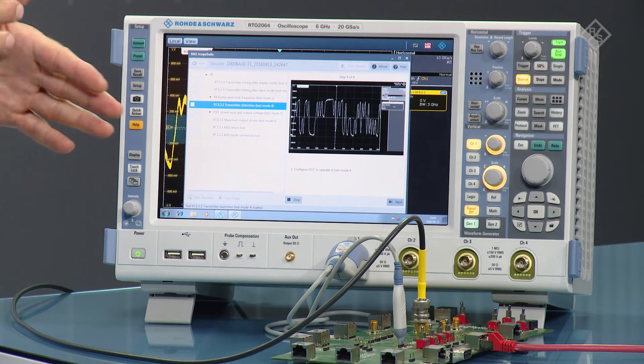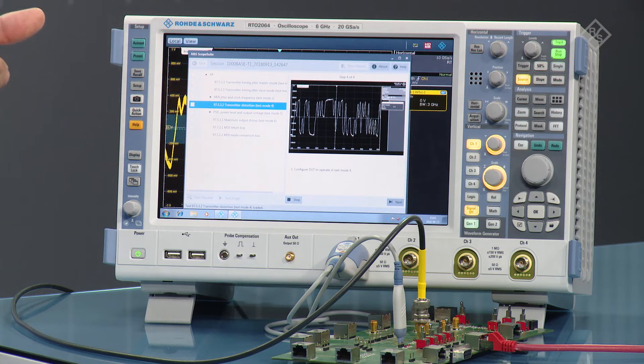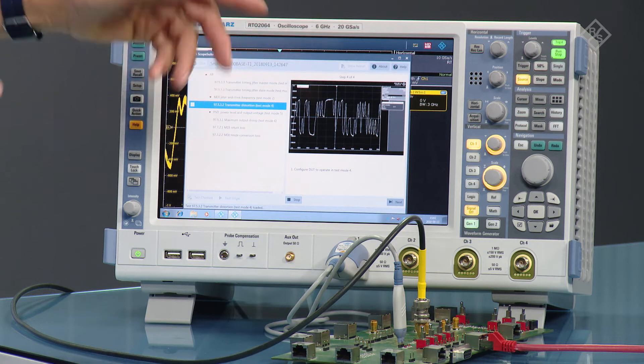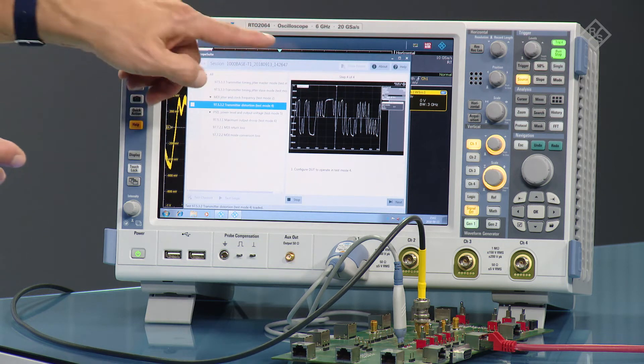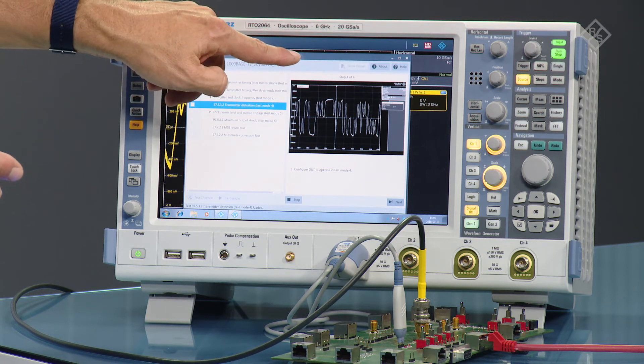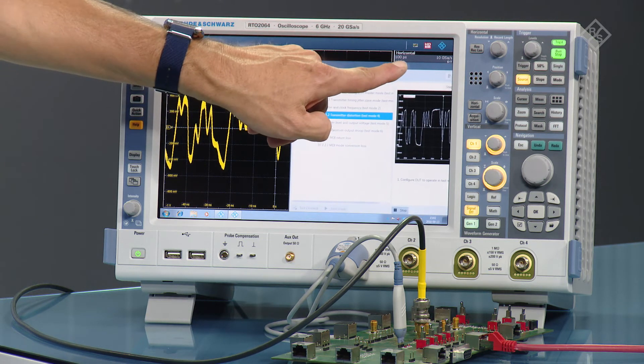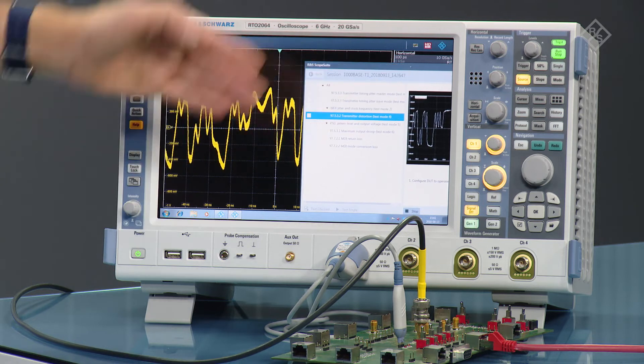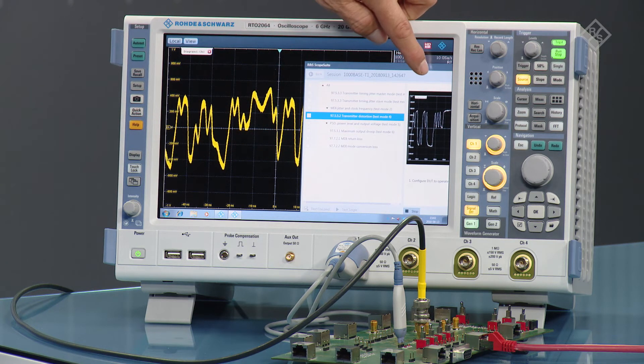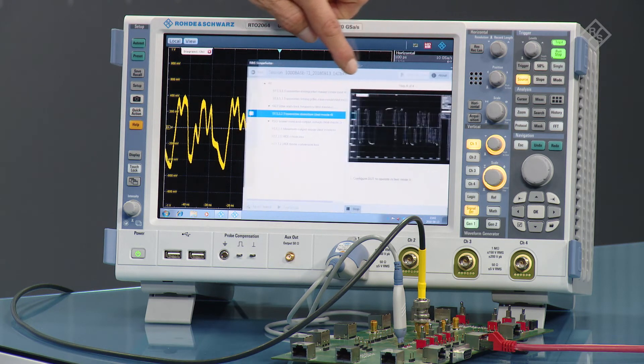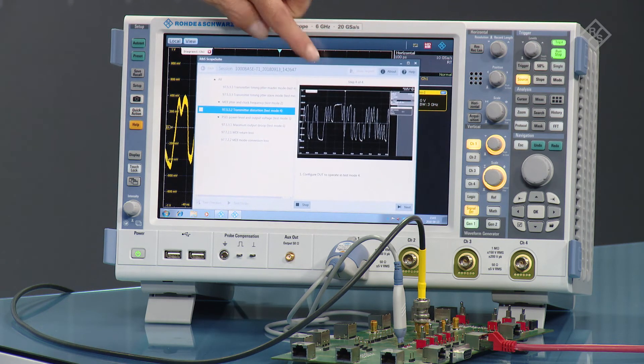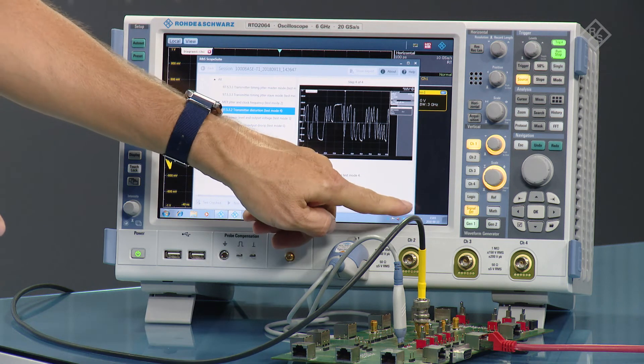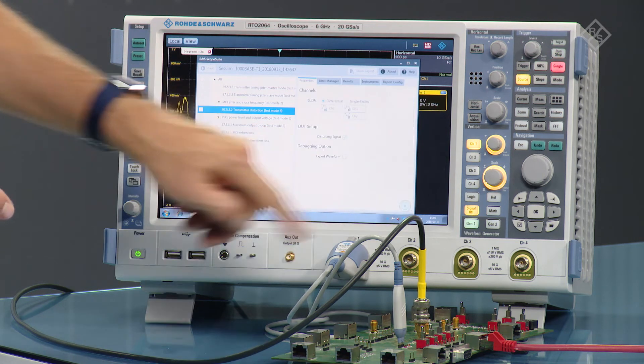Now the software asks you to configure the DUT in test mode 4. And you see a screenshot of what you should see and expect to see on the oscilloscope. So I go back and you see this is exactly the same signal, so we have the correct test mode 4. Now I run the test.